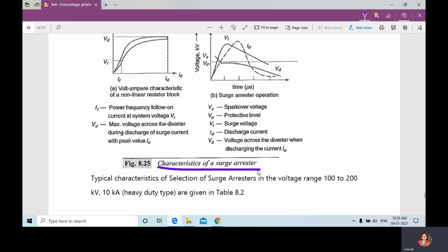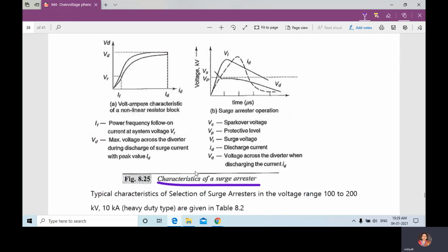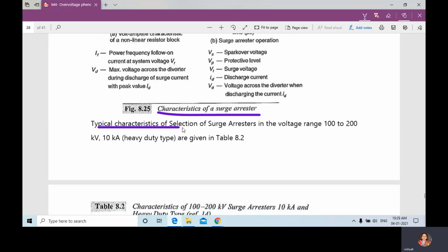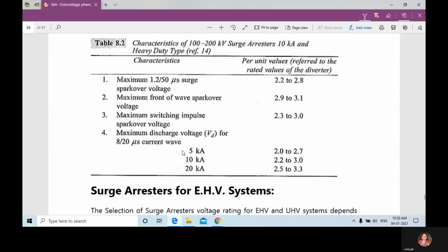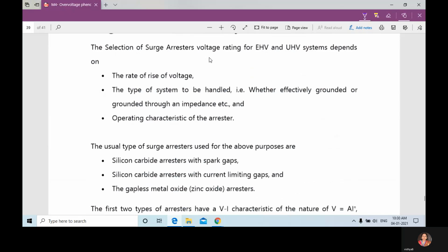Characteristics of a surge arrestor. These are the characteristics of a surge arrestor. Typical characteristics of a selection of a surge arrestor in the voltage range of 100 to 200 kV and 10 kiloamps, that is heavy duty type. This is the table for characteristics of a 100 to 200 kV surge arrestor, 10 kiloamps, heavy duty type.